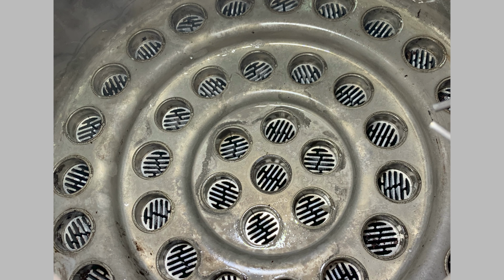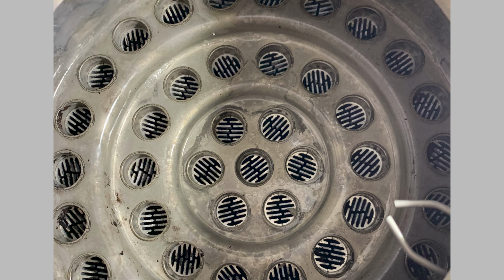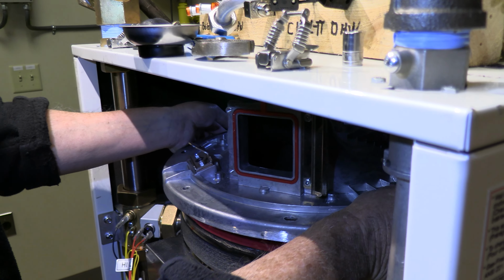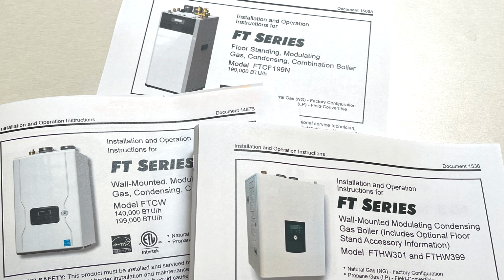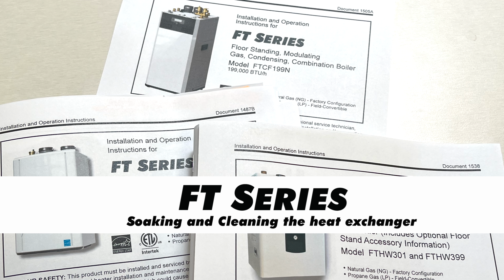The final step is to use a plastic brush to scrub the burner chamber and to use water to rinse the heat exchanger fully until you have obtained a nice clean heat exchanger again. Dispose of the rinse water properly. Once a clean heat exchanger is achieved, remove the tube and save it for your next FT series cleaning. Reassemble the condensate trap into its location and reassemble the top of the boiler using the exact reverse of its disassembly. Follow the startup procedures as shown in the installation and operation manual, and if you have any further questions, please call the manufacturer.